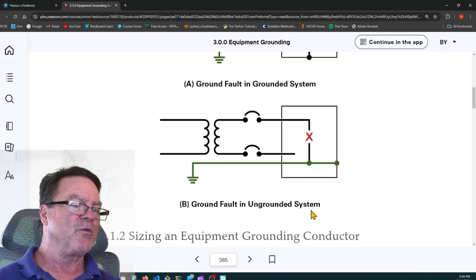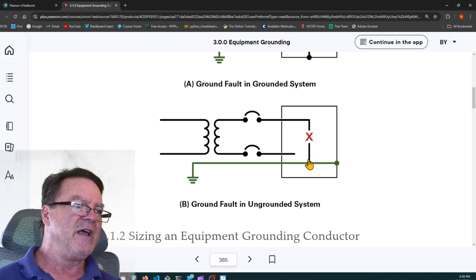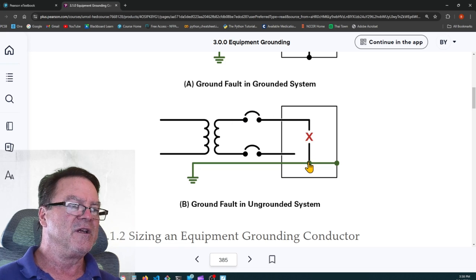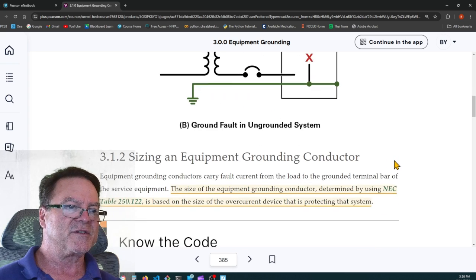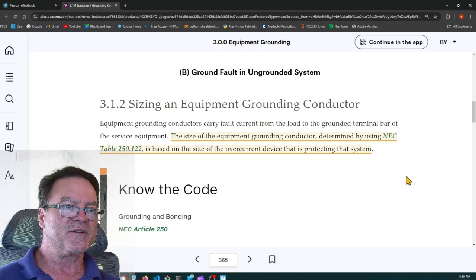Here's a ground fault in an ungrounded system. This system is not normally grounded, but the secondary side of this 2-pole circuit breaker has the return, and it takes it to ground, so that if something does occur, we have an equipment ground going to earth ground on the load side of the circuit breakers, so that we'll have enough fault current flowing in order to trip this circuit breaker and disconnect it, even on an ungrounded system.